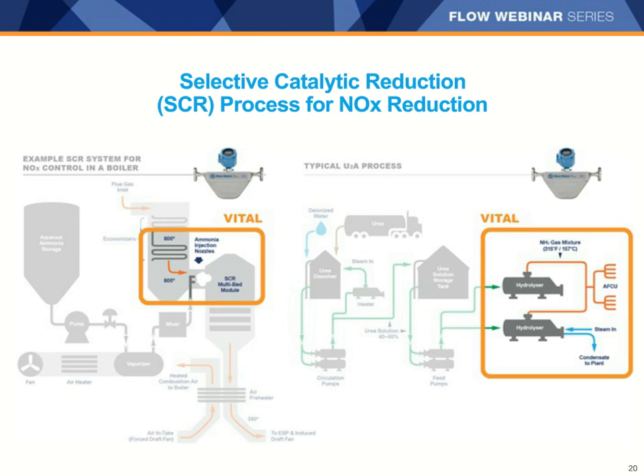Selective catalytic reduction is a means of converting nitrogen oxides, also referred to as NOx, with the aid of a catalyst into nitrogen gas and water. A gaseous reductant, typically anhydrous or aqueous ammonia or urea, is added to a stream of flue or exhaust gas and is passed through a catalyst bed.